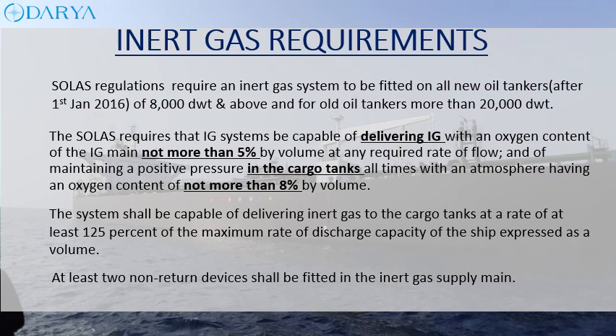SOLAS regulations require an inert gas system to be fitted on all new oil tankers after 1st January 2016 of 8,000 deadweight and above, and for old oil tankers more than 20,000 deadweight. IG systems must be capable of delivering IG with an oxygen content of not more than 5% by volume at any required rate of flow, and of maintaining a positive pressure in the cargo tanks at all times with an atmosphere having an oxygen content of not more than 8% by volume. The system shall be capable of delivering inert gas to the cargo tanks at a rate of at least 125% of the maximum rate of discharge capacity of the ship expressed as a volume.